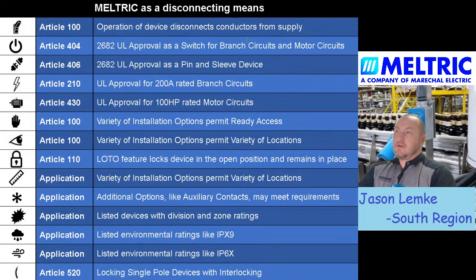Then you'll see some applications refer to the disconnecting means needing to be switch rated. So when that happens, sometimes you can use molded case circuit breakers, sometimes you can use a standard disconnect switch, and you can also use a Meltric device because it is approved for a switch. Sometimes a disconnecting means can be a plug-in receptacle, and oftentimes you'll find that there is no further requirement in the application than being a plug-in receptacle.